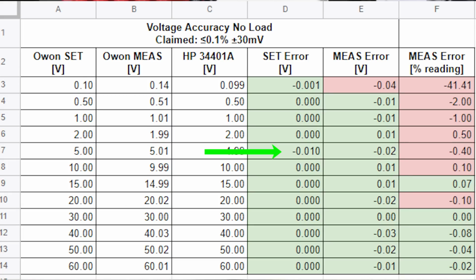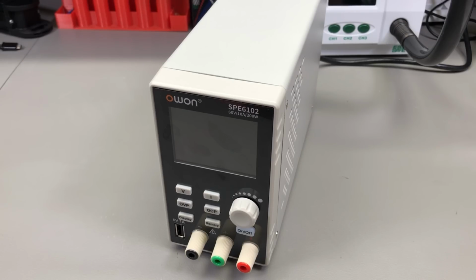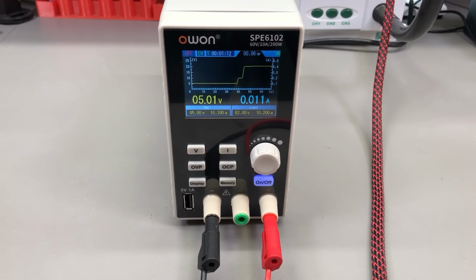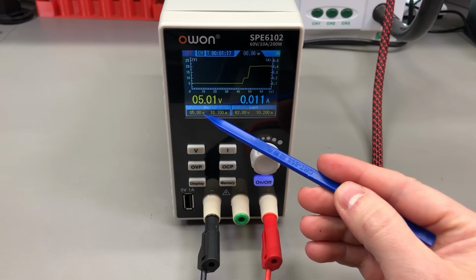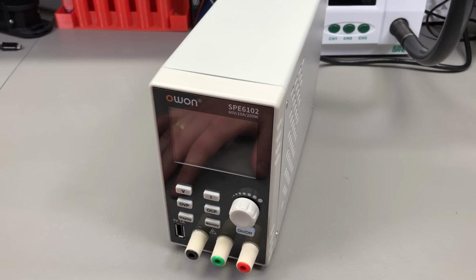Now remember, the claimed spec is better than 0.1% plus or minus 30 millivolts, and what's strange is that the measured accuracy, so what's shown in the middle of the screen, is much worse. I mean, it's only outside of spec for the very low ranges with 40 millivolts, but I find it strange to see different values between set and measured voltage with no load. It just makes me think that they might be using two measurements or measuring in 2 points, one for the set and control loop and another one for the measured displayed value. And the two do not correlate, but I would love to hear your thoughts in the comments about this issue.